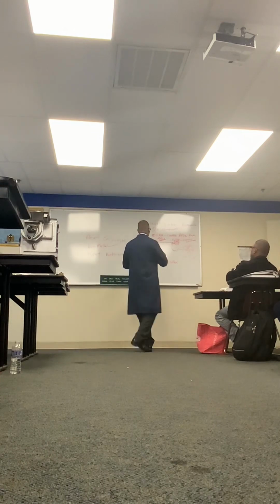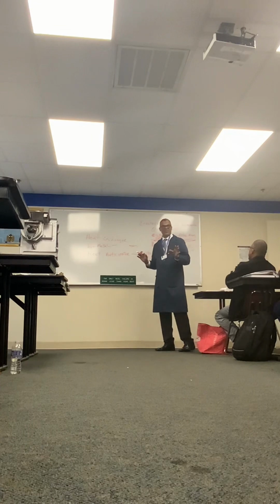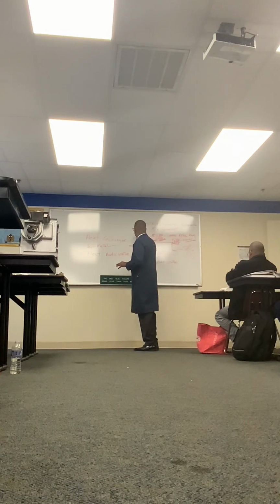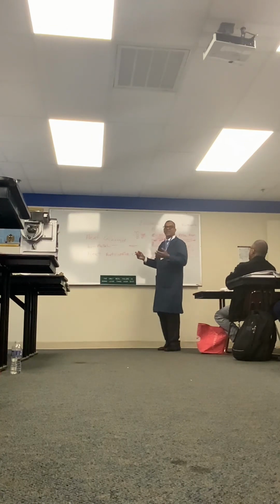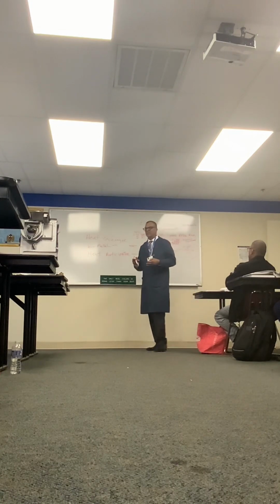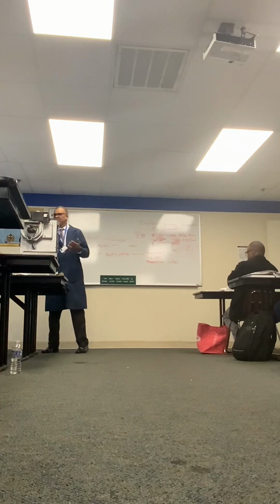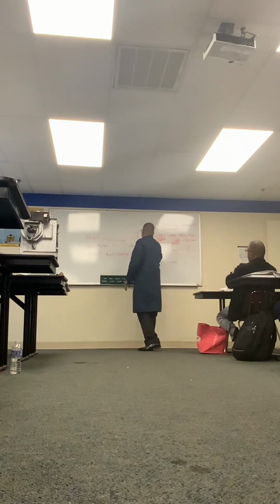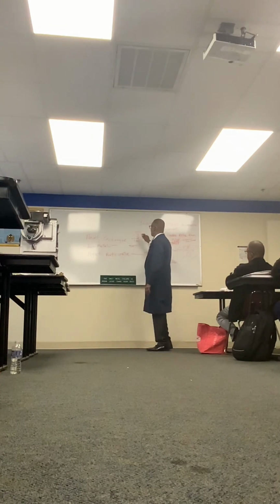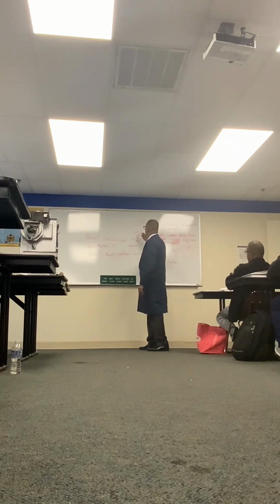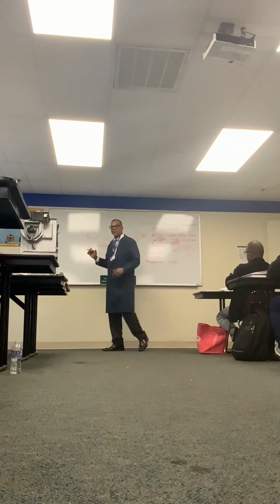Okay, so I'm explaining to you what that means, a 400 amp service. Okay, 400 minus 50 for the dryer, electric, 50 for the stove, 50 for the AC, and then all the other little outlets that you're running in your house. Some are 10, 15, 20, most of them 15, 20. So you add these up, and we're already at 150. So you took away 100, that's 300, take away 50, that's 250. So we only have 250 amps left for the whole house.